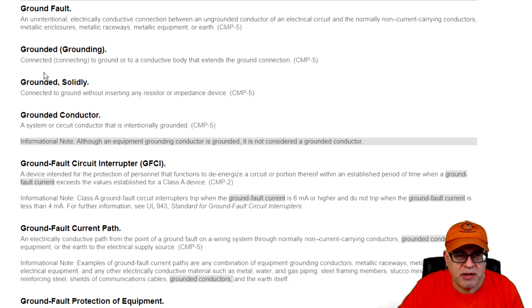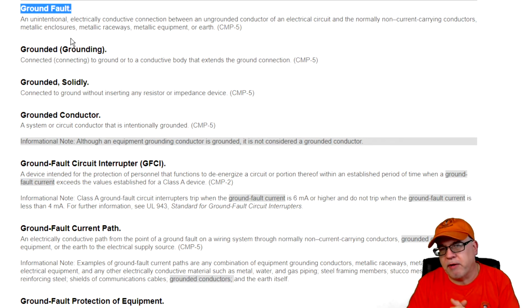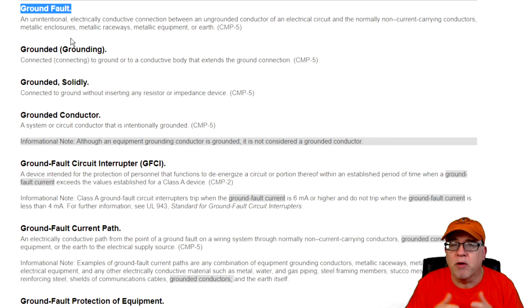We have definitions. Ground fault. Real important. We understand what a ground fault is. We also heard earlier short circuit and a ground fault, all of which are still part of an overcurrent condition. Overcurrent is made up of three components: ground fault, short circuit, and overload. All of those make up overcurrent. So what is a ground fault?